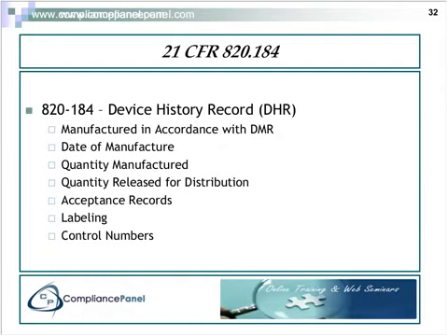It's important that all the required information for materials is recorded so that if a recall is necessary, you'll have specific knowledge of where the affected devices are located. Now again, the level of component detail that you go to in your device history record is up to you. You can take it all the way down to a screw or a resistor on a circuit board.